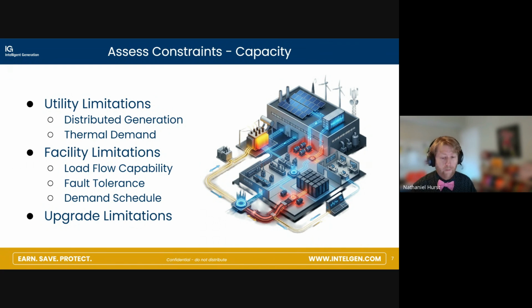This is really important with batteries: when you connect them, you need to ensure the existing facilities aren't overloaded. It's also important for your service drop to make sure the utility itself isn't overloaded, and to understand what level of control and protection is needed to stop that. In certain situations, that might be as simple as adding another breaker that clamps everything in and out of the utility.